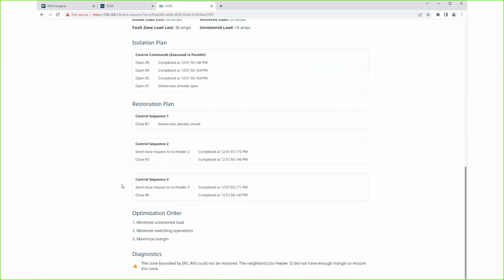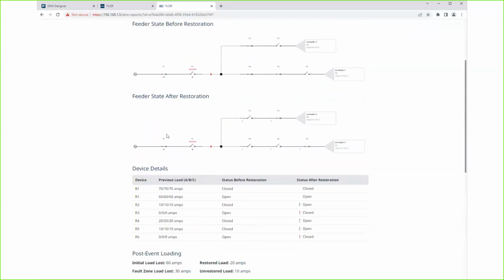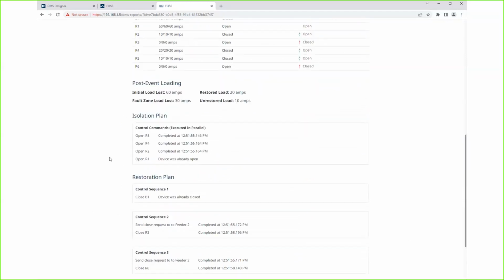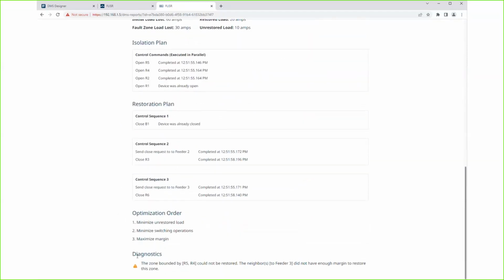So it'll tell you at the bottom, this zone bounded by the following devices could not be restored. The neighbor didn't have enough margin. So we can walk through exactly what it did to restore and isolate, where the fault boundary was, and if there were a problem, if it wasn't able to do everything you thought it should be able to do, it will explain itself, which is pretty helpful if you weren't watching it at that time.